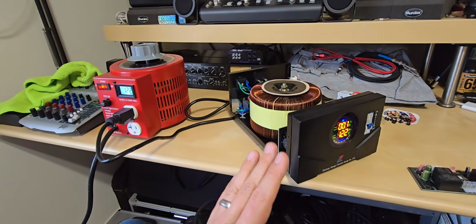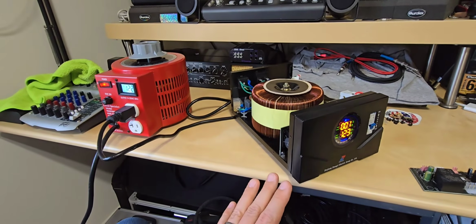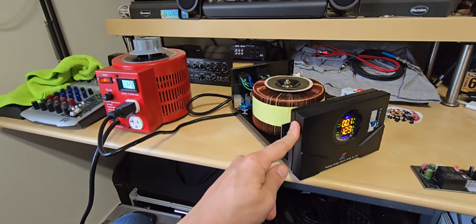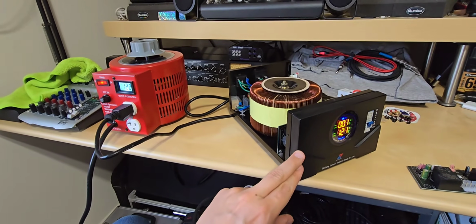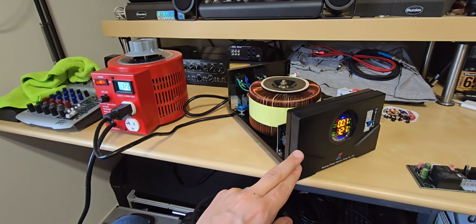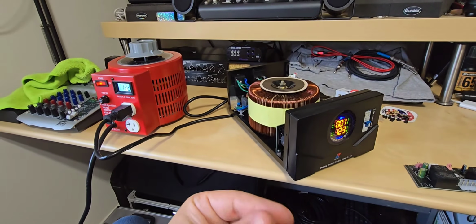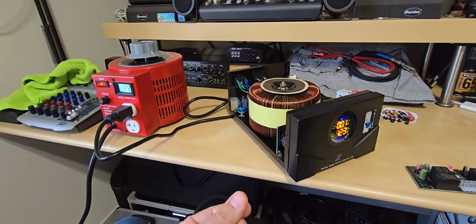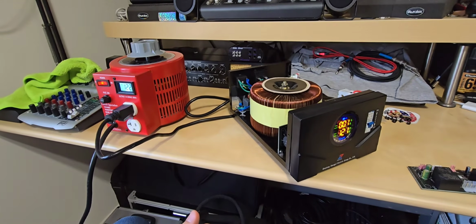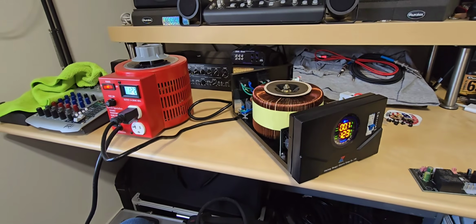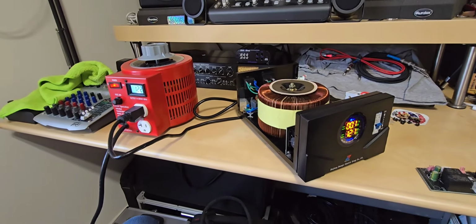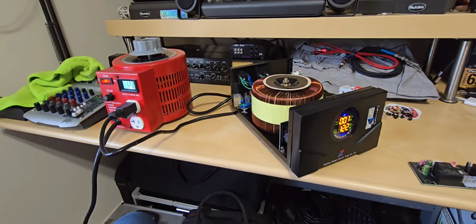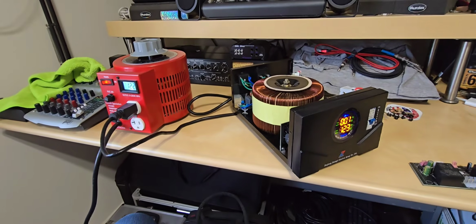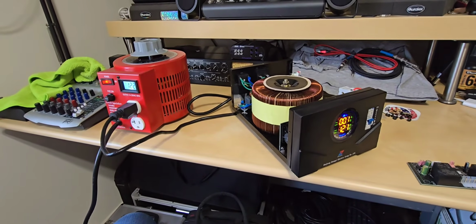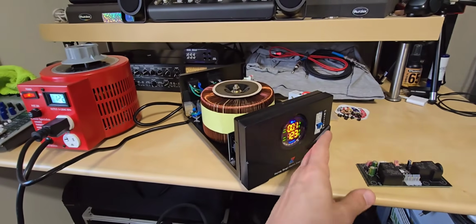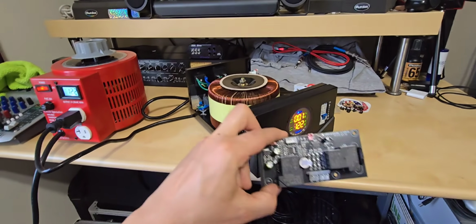Initially they had sent me an updated program hex file to reflash the microcontroller that runs all the advanced features such as the overvoltage and undervoltage protection, and they said that it was programmed to the proper set points, which I requested: 132 volts on the overvoltage and 105 volts on the low voltage. However, when I went looking for a programming tool, I just didn't have a lot of luck, and what they were able to do is sell me this new updated control board.